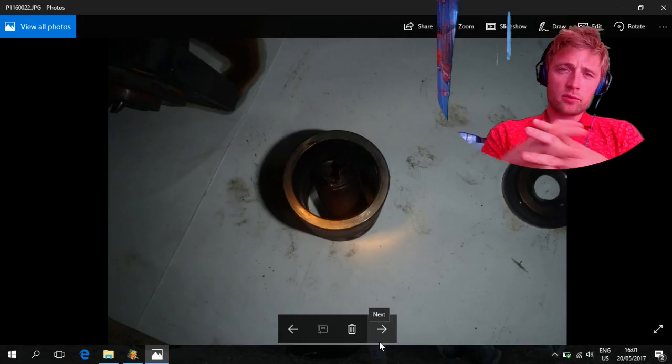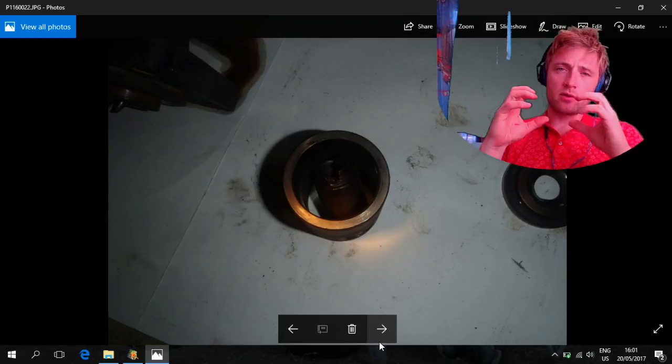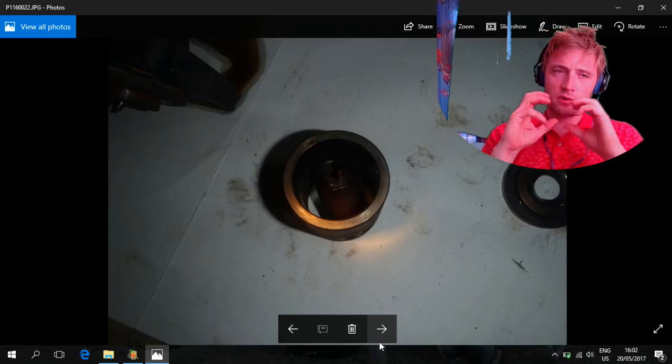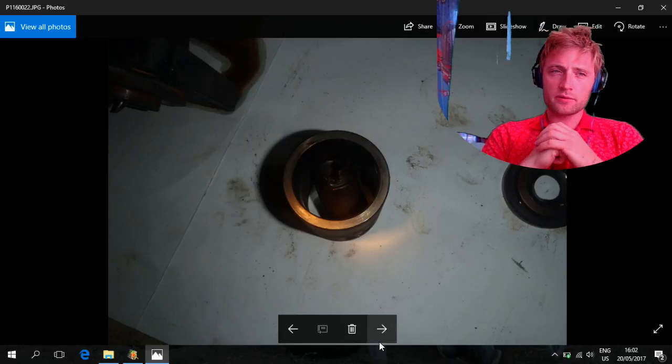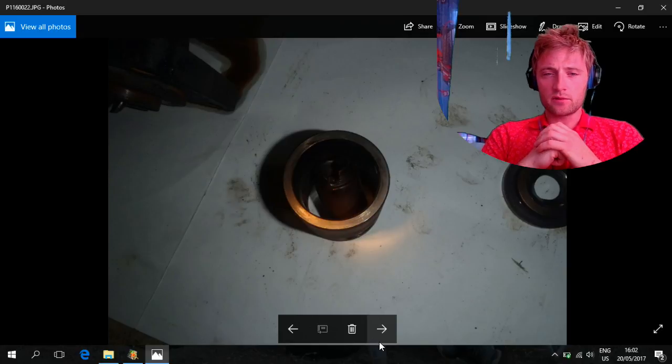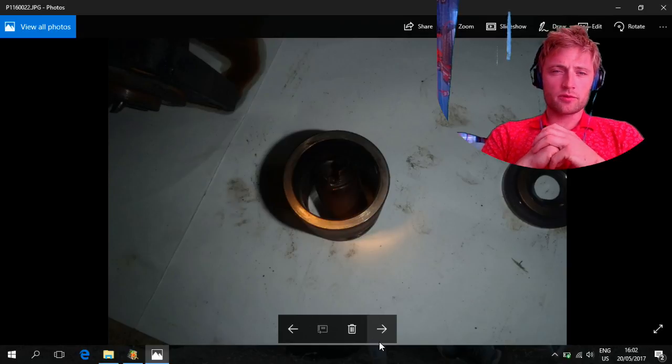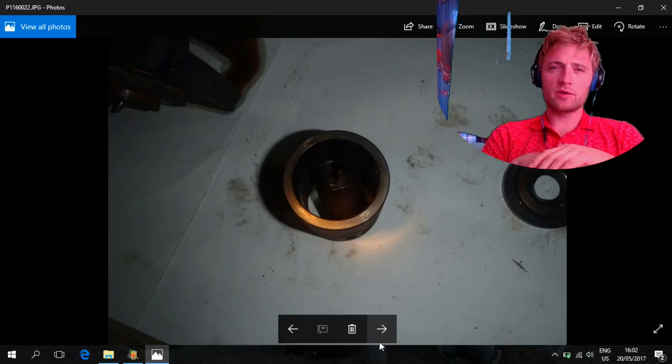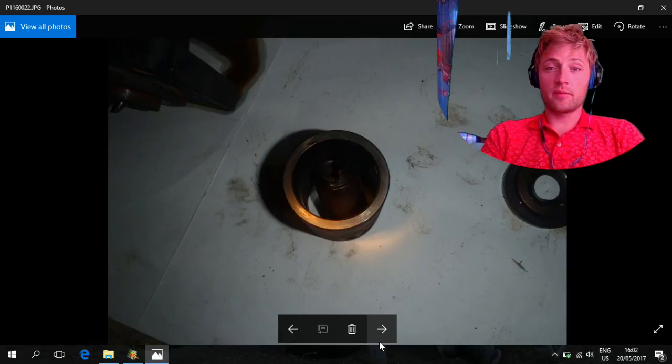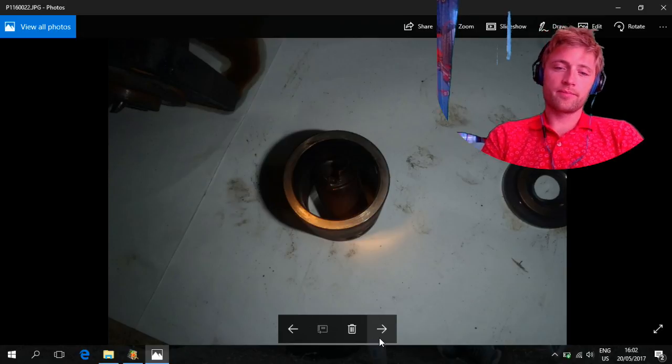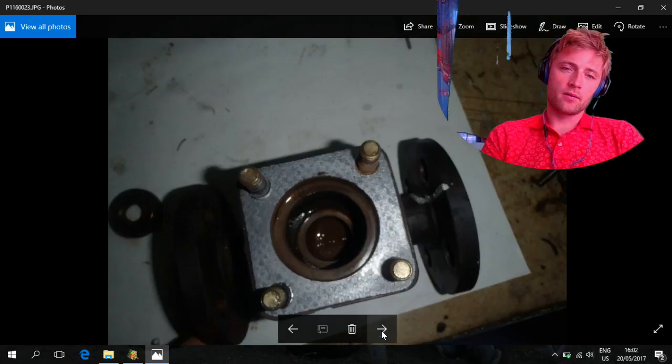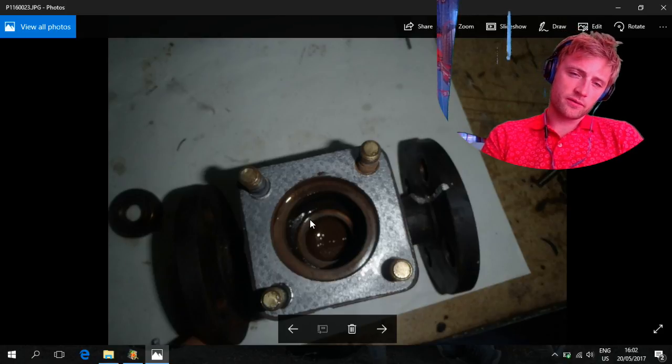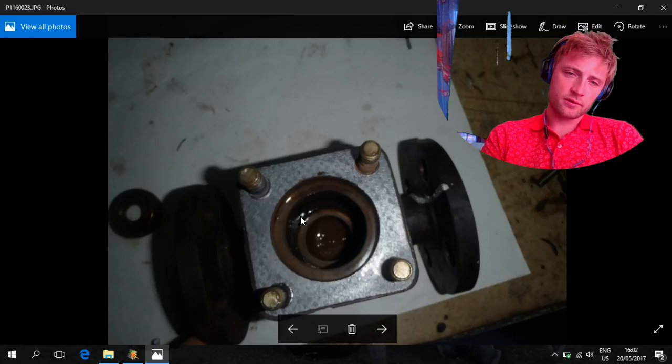If you also have your valves closed small, very little closed, it's not good because the steam passing makes damage to the seats and the metal. Just remember that.